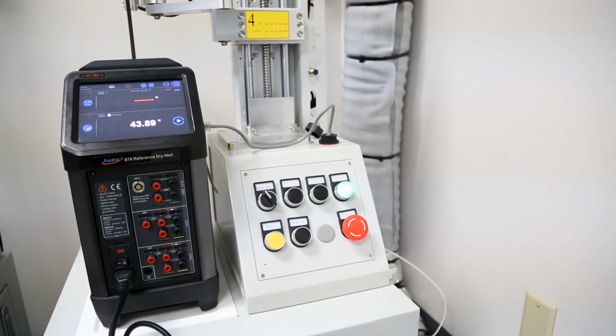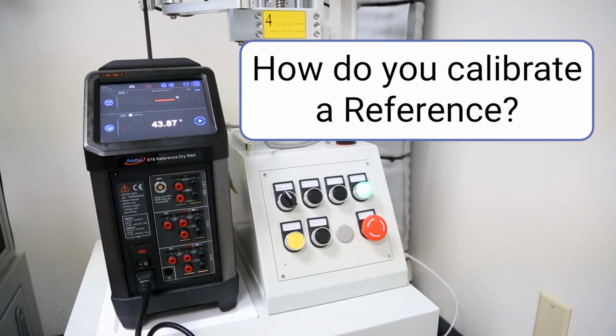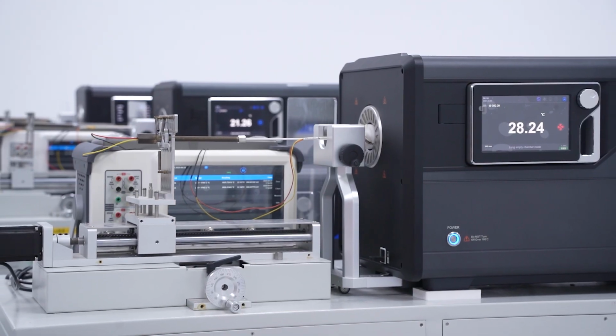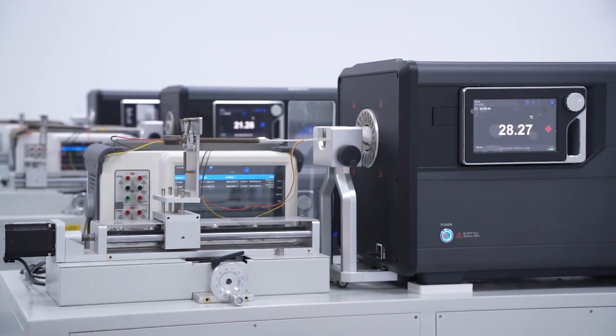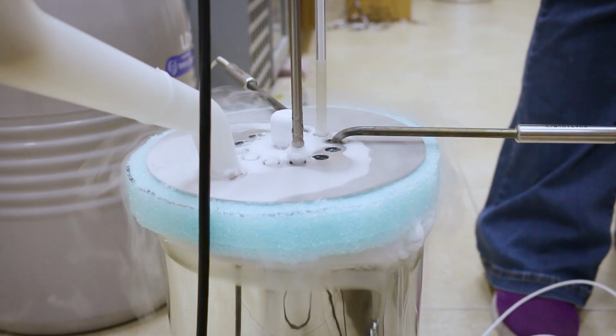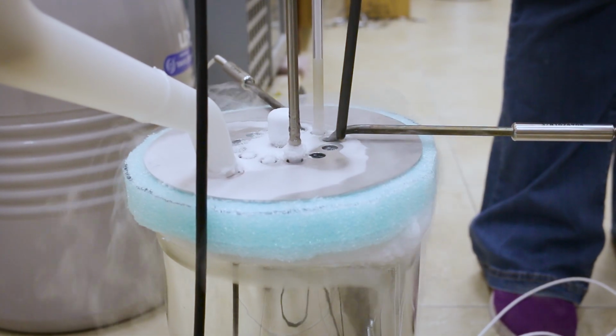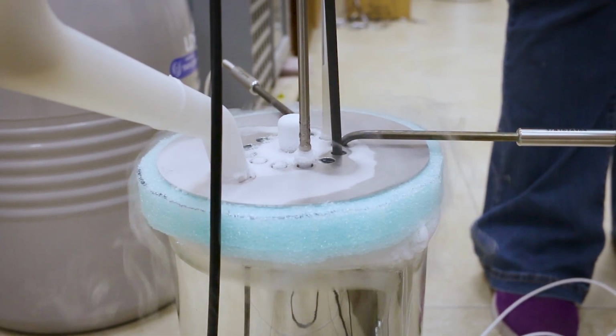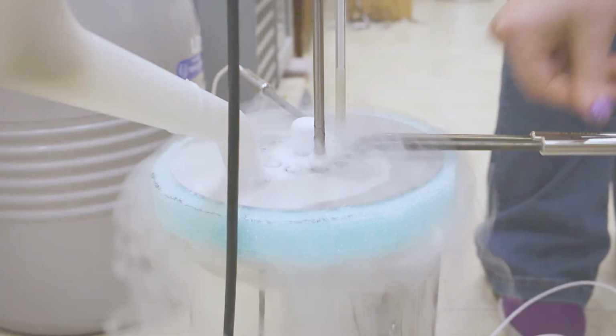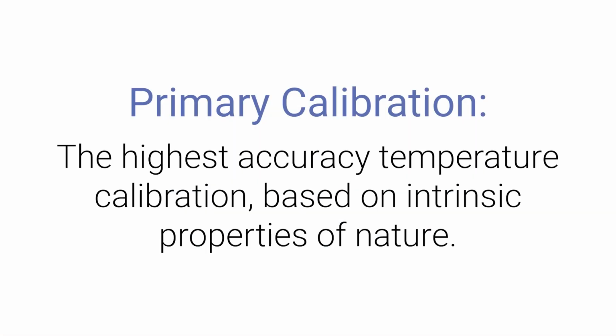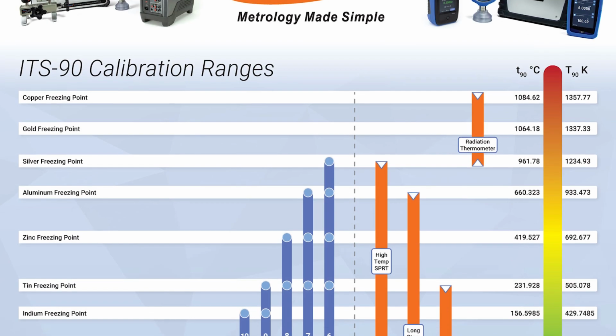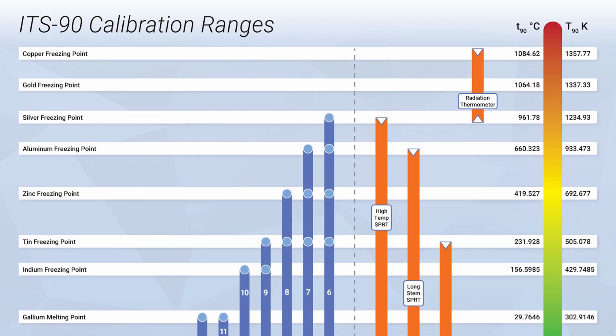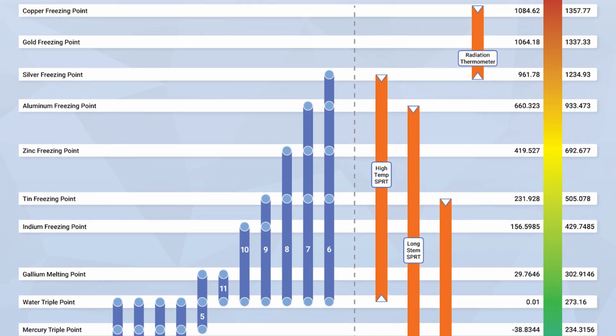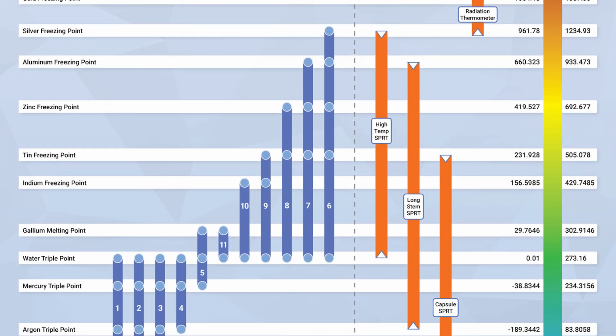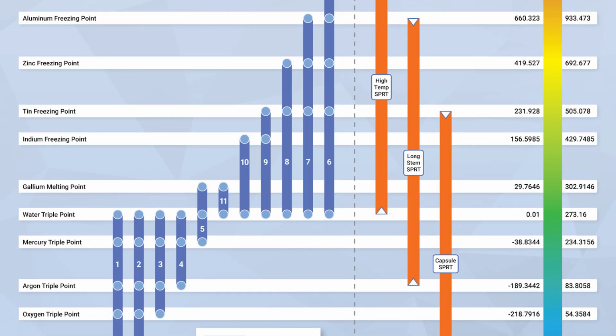But you may still be wondering, how do you calibrate a reference? These high-accuracy measurement devices need to be sent to a temperature calibration laboratory, where they will be calibrated against intrinsic physical properties of nature in controlled conditions for maximum accuracy and repeatability. This is referred to as a primary calibration. By using these intrinsic standards, primary calibrations can remain in compliance with the 4-to-1 calibration rule, despite the increasing accuracy requirements of the unit under test.